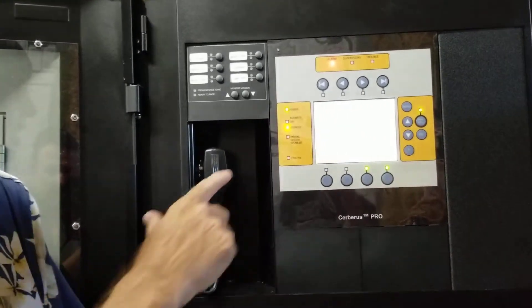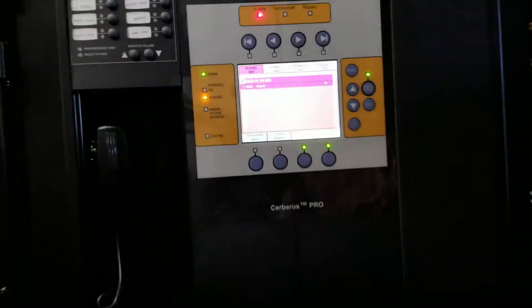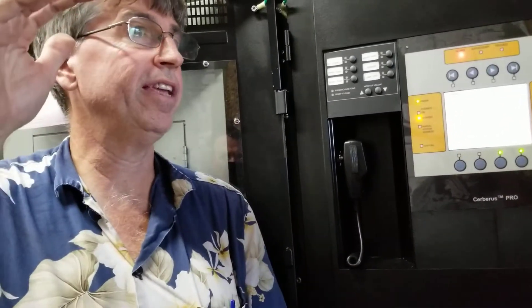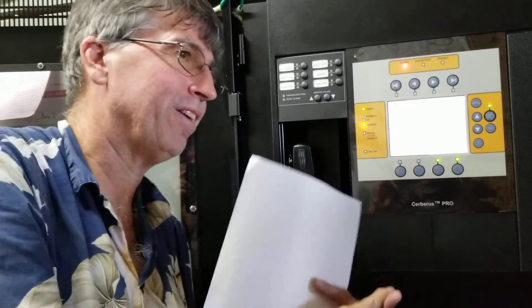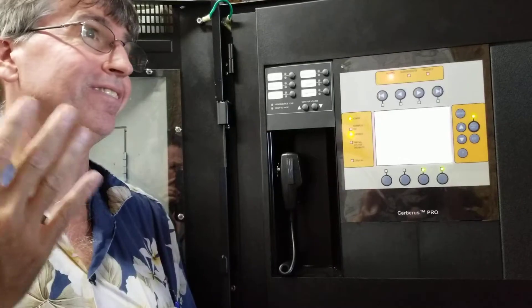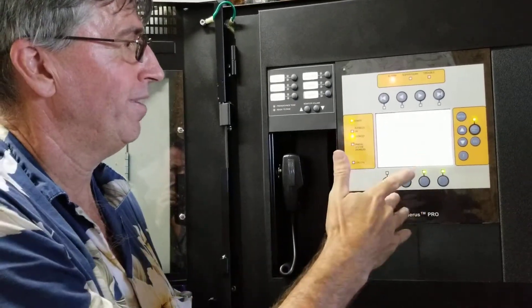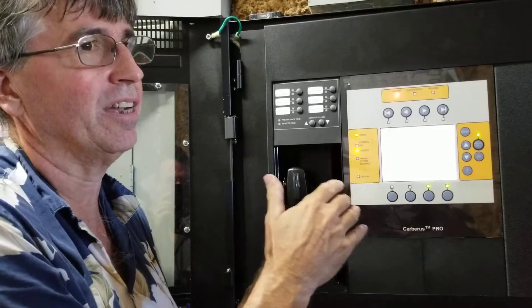It said ground floor, and it will tell you exactly where it's at. The panel won't reset if the device isn't reset. If the alarm goes off, the elevator — that's only the smoke detectors that are in the elevator lobby. The fire alarm panel has to be reset, and then the elevator is going to reset. For smoke detectors, if you hit reset and it's still in alarm status, it's just going to go into alarm again. This is the status you want to be in until you positively identify the cause of the fire.